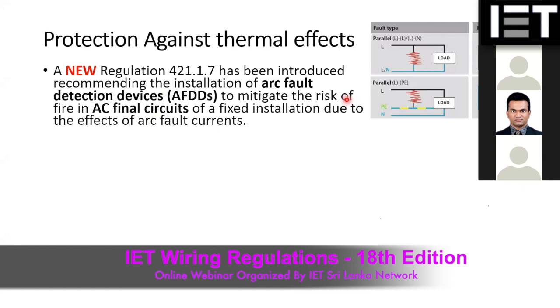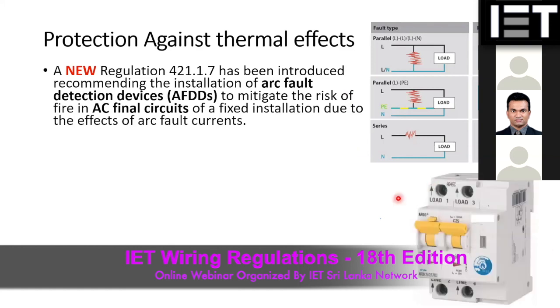But when you look at the third type, that is the series faults. There can be certain types of disconnection or loose connection where that can create sustained arcs within the installation. Even an MCB or RCD or any other device will not detect this type of arc fault, and people realized that this will lead to fire. Because of that, in the new regulation, a new device is introduced, the arc fault detection device. So only this third category can be detected by the arc fault detection device. That's why it is introduced. And these are similar kinds of devices.